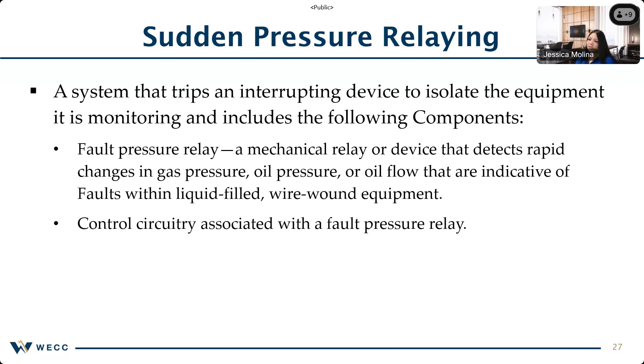And lastly, sudden pressure relaying. So this is a system that trips an interrupting device to isolate the equipment. It's monitoring and includes the following components. So one is a fault pressure relay. This is a mechanical relay or device that detects rapid changes in gas pressure, oil pressure, or oil flow that are indicative of faults within liquid-filled wire-wound equipment. And it's also control circuitry associated with fault pressure relays. Next slide, please.